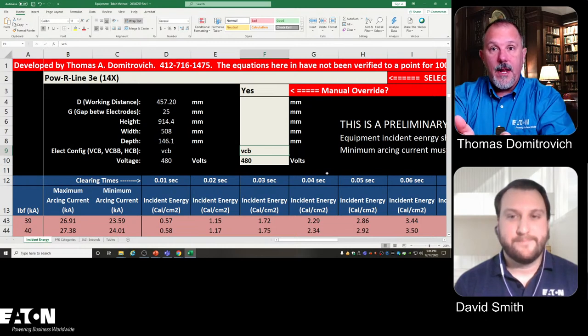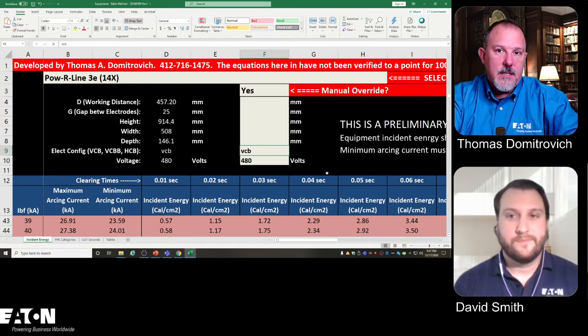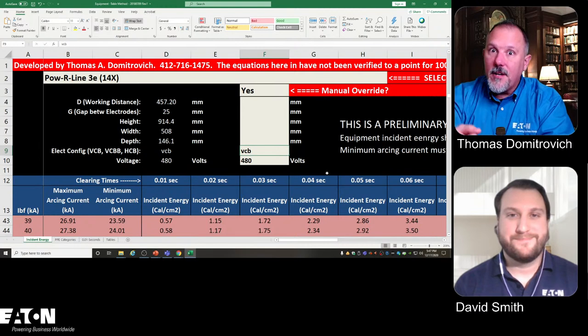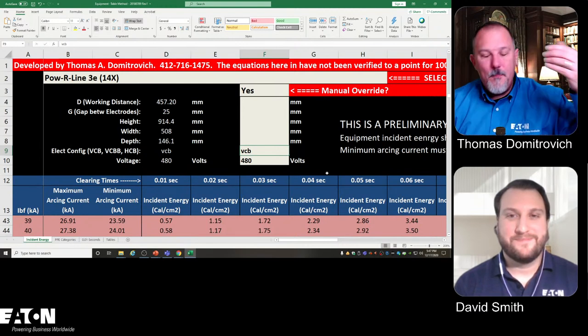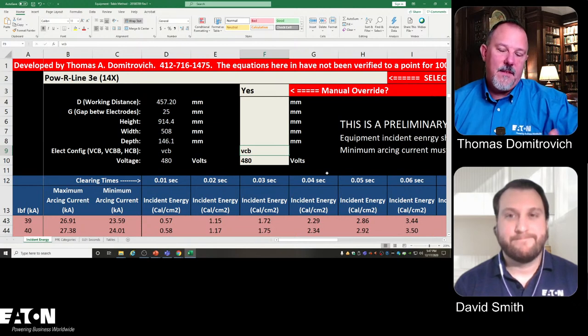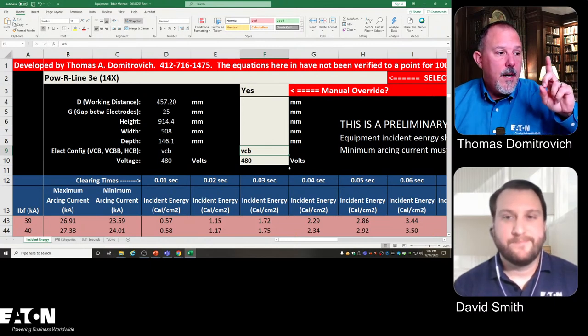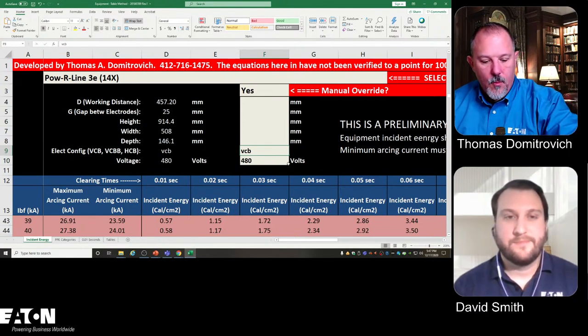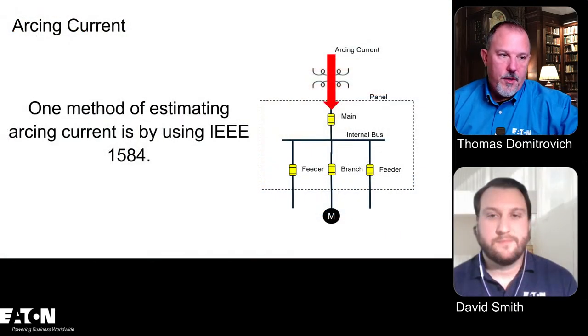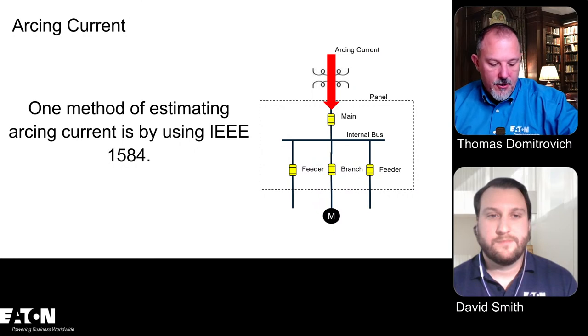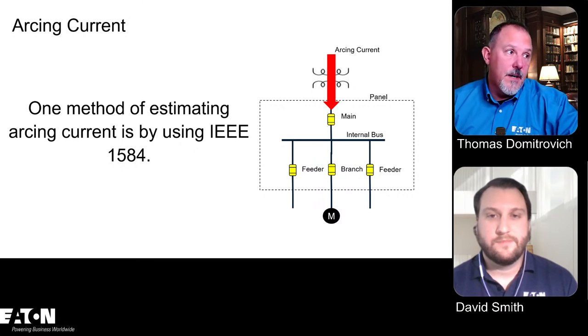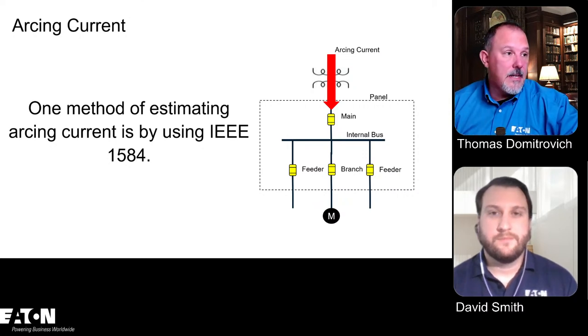Yep. My voltage isn't 480, my voltage is 208. I can use a 600, 800 amp breaker on a 208 volt system. I can use an 800 amp breaker on a 480 volt system, but my arcing current's gonna be much less on the 208. I'll have a better chance of being in the long time region outside of the instantaneous on a 208 than I will on a 480. Exactly right. So this gives you a little flavor for what it does for you with regard to the amount of incident energy. So the size of that overcurrent protective device, whether it's an 800 amp breaker or a 1200 amp breaker, if your arcing currents are less than the instantaneous, you've got problems.